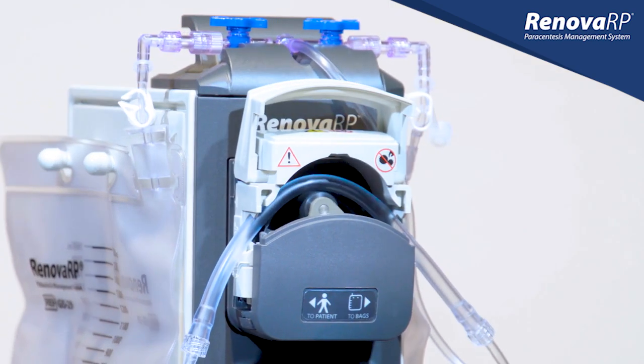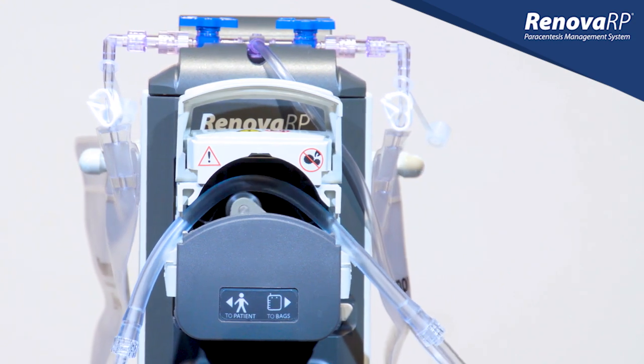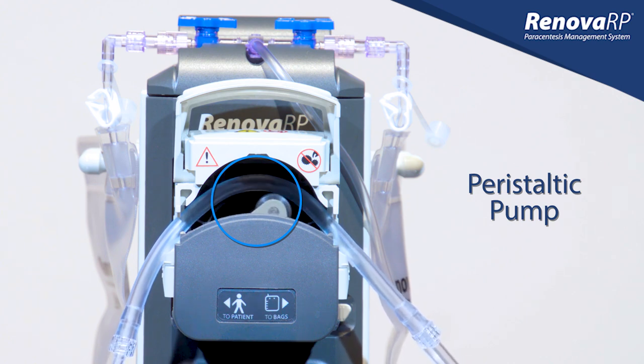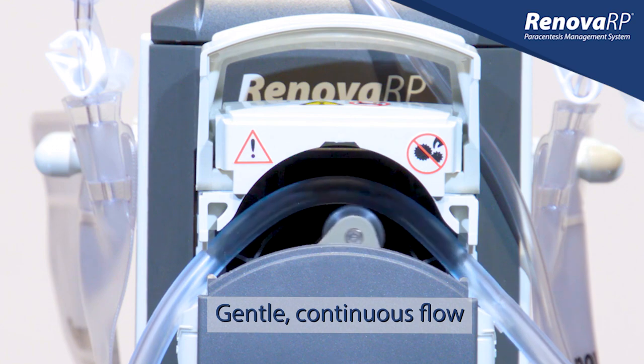Many of these benefits, including its efficiency and adjustable flow rate, come from the mechanism that drives the device — a peristaltic pump. Peristaltic pumps are fairly common in the medical setting and can be found in such devices as infusion pumps and dialysis machines. The Renova RP Pump employs this same peristaltic mechanism to draw ascitic fluid from the body with a gentle, continuous flow.